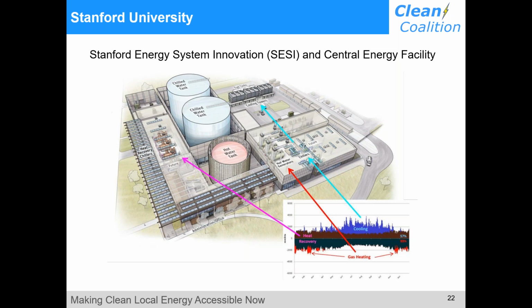So the Central Energy Facility takes advantage of that overlap in needs through heat transfer via the chilled water tanks and hot water tanks you see here. That heat recovery process, where you have the overlap between cooling and heating, takes place on the left side of the facility, where they're swapping thermal energy between hot and cold. If they need additional heating during winter months, there are hot water generator heaters, and for cooling, they have capacity through chillers and cooling towers.